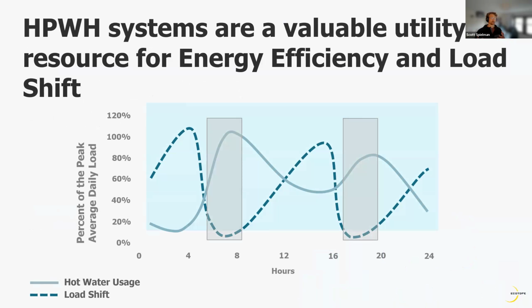So one of the things that's nice about hot water systems is we've got a large thermal storage volume inherently built in, especially when we're using a heat pump water heater, because when we design with a heat pump water heater, we can add to the storage volume in order to provide less capacity on the hot water generation side from the heat pump. And that both helps the heat pump from an operational standpoint because it has a more stable, long period duty cycle, which is beneficial for the longevity of the compressor in the equipment. And it helps us with load shifting because that large thermal storage tank can be a thermal battery that we can use to shift load.